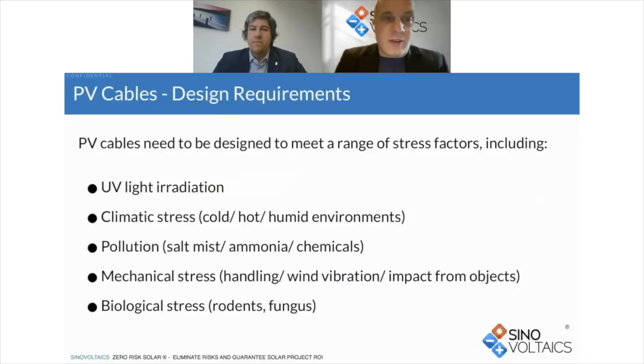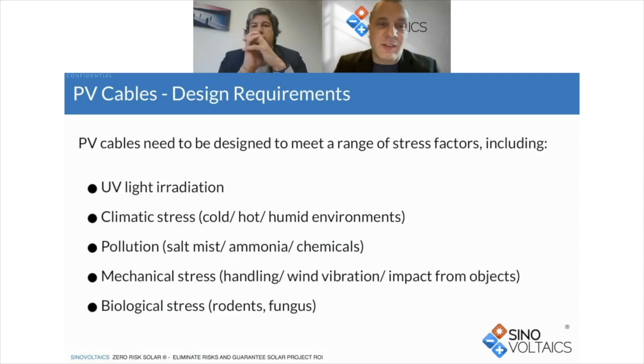On the topic of PV cable quality, it is important to understand that PV cable differs from standard power cables and is a fairly new addition to the industry portfolio of cables used in diverse industrial, commercial and retail applications. So in connection with the interconnecting application in solar PV power plants, and therefore with a lifespan of 25 and more years in mind, PV cables generally need to meet a range of very stringent design criteria that in particular address outdoor stress conditions. And these include UV light resistance, being acid and base proof, moisture and extreme temperature resistance, mechanical stress forces such as wind vibrations or compression, bending, and also biological factors stemming from rodents and fungi.